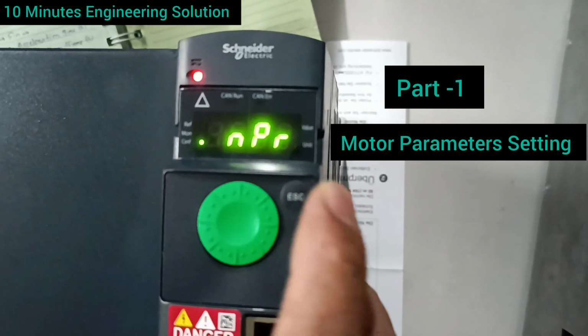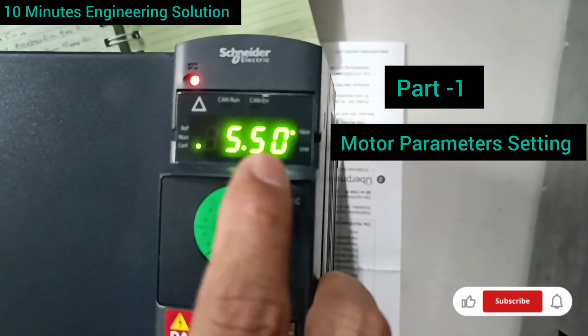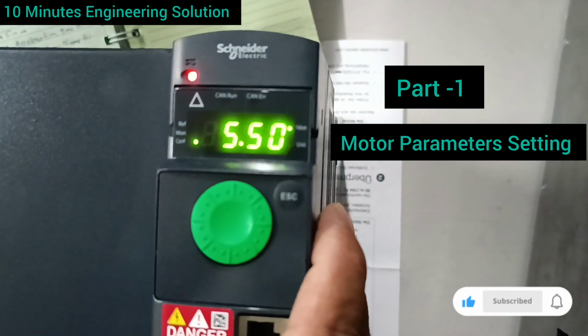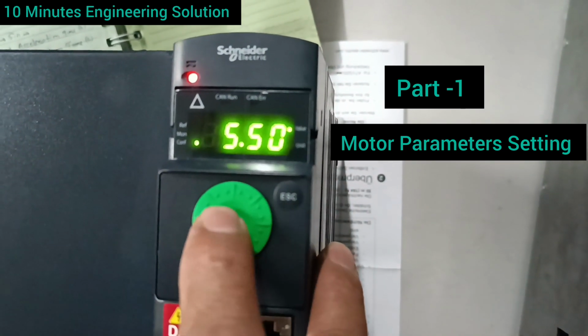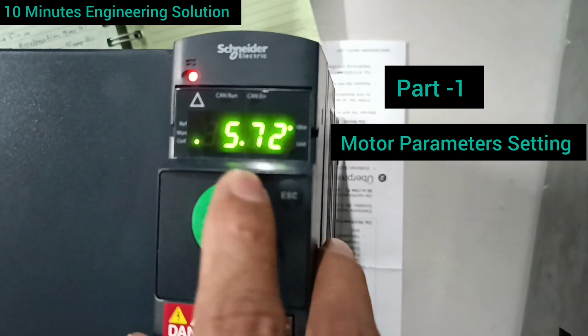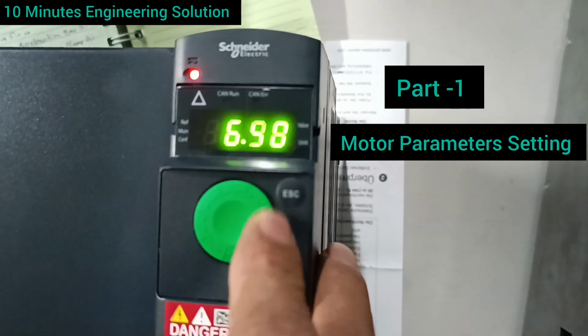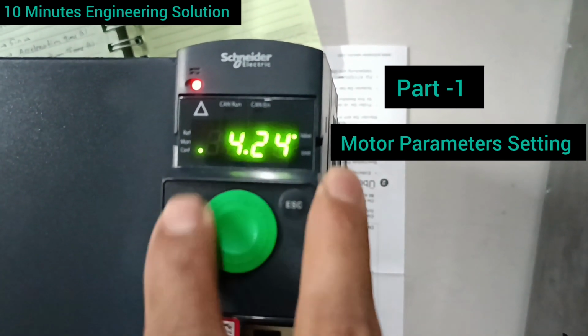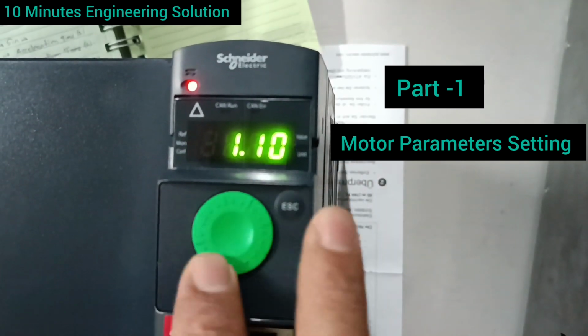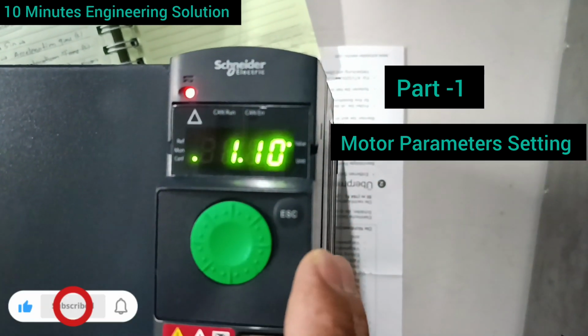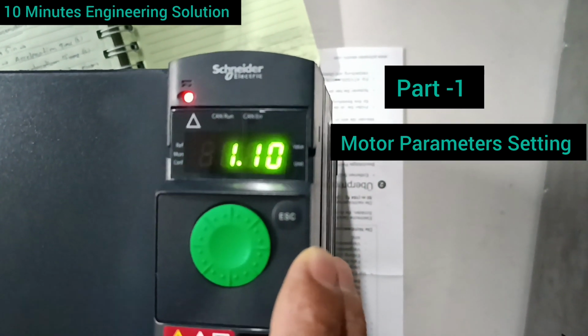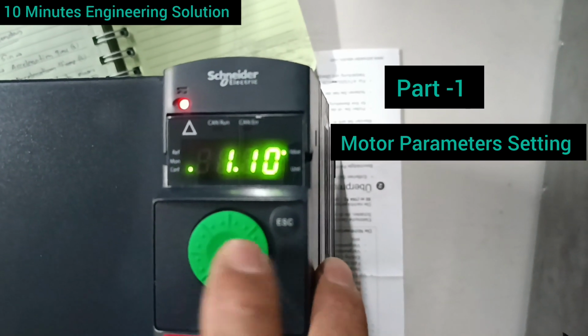Now NPR, you can see the picture in here. This is the rated motor power. The VFD is 5.5 kilowatt in my system, but my motor is 1.1 kilowatt, so I have to reduce the sizing of this VFD. So 1.1, you can see the picture in here. I just set it to 1.1 and then enter.